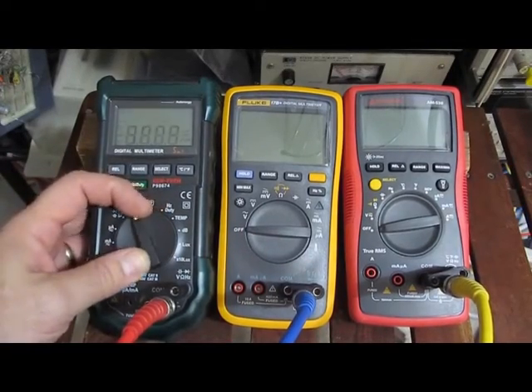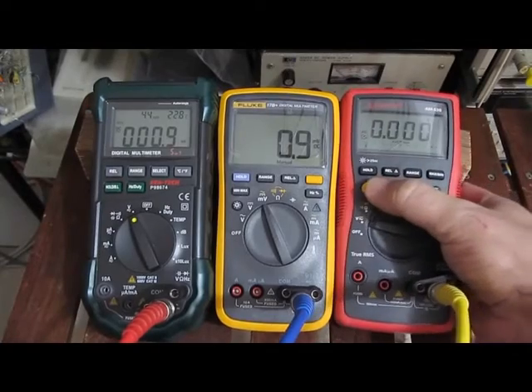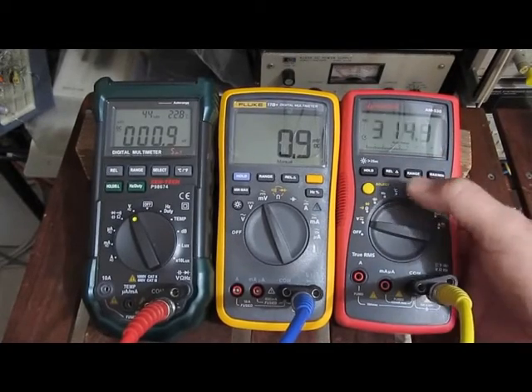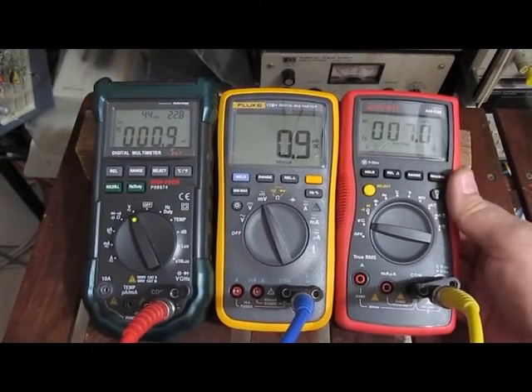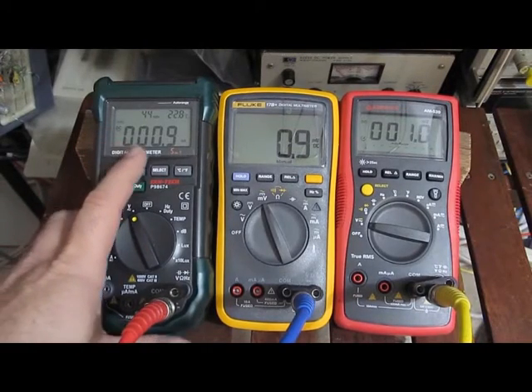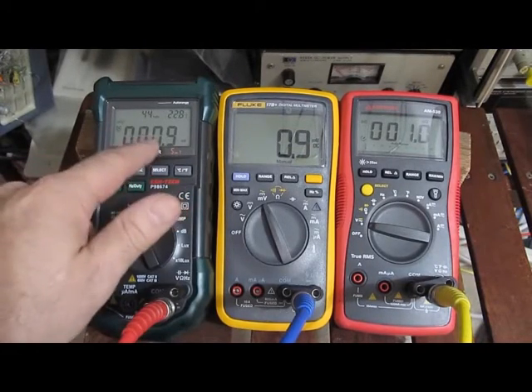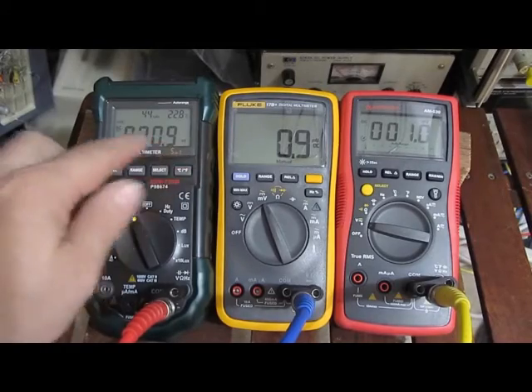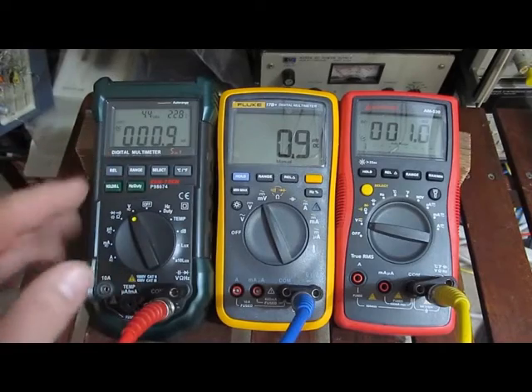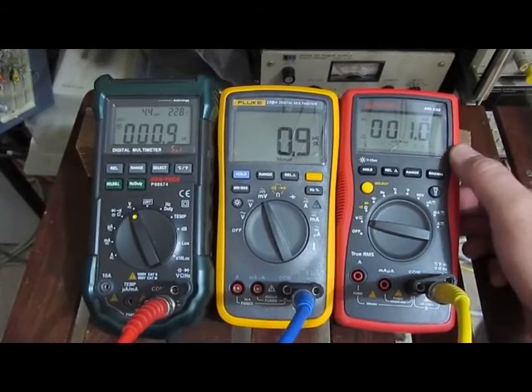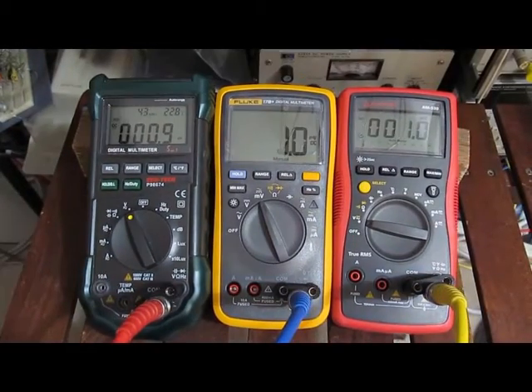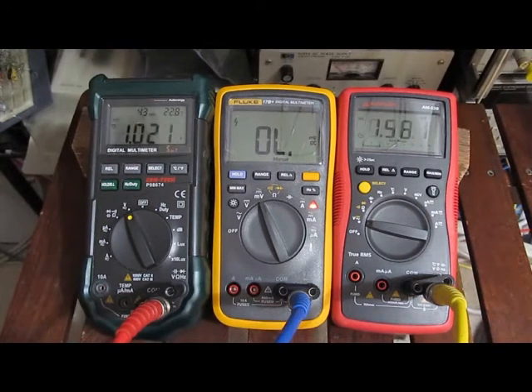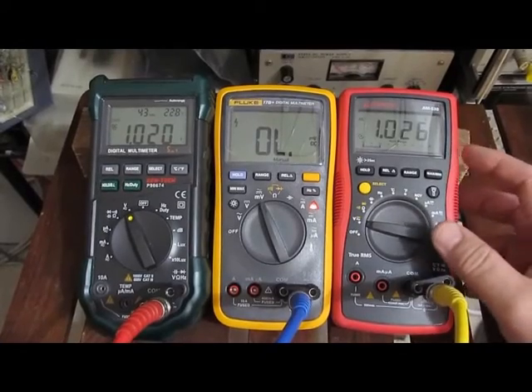These three meters are tied in parallel and they're attached to my Fluke reference. You can see the Amprobe comes up with AC volts, so it has to be selected to DC. Putting out a 1 millivolt signal right now. We can see here it's reading 0.9 on the Mastech, 0.9 on the 17B Plus, and 1.0 on the Amprobe 530. And now I'm going to select 1.019 volts. You can see the Amprobe's off by a little bit now.